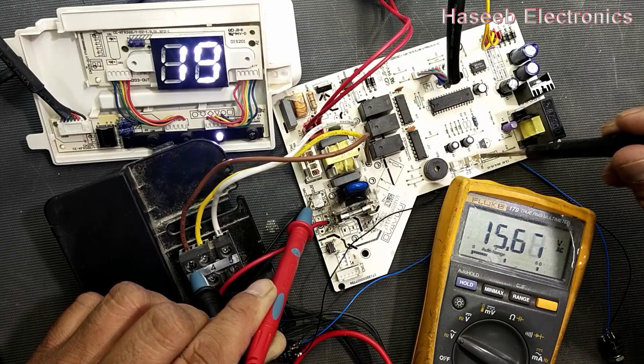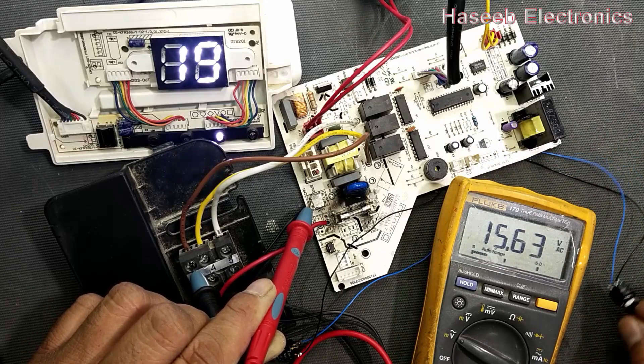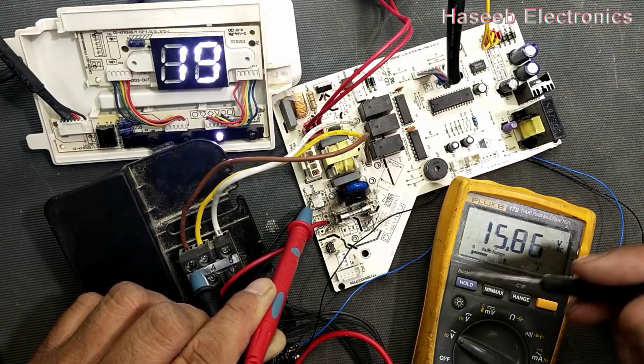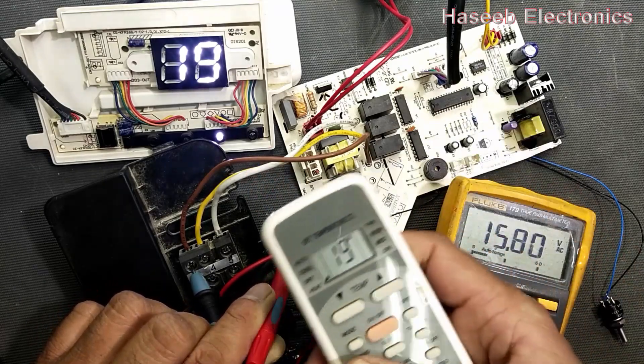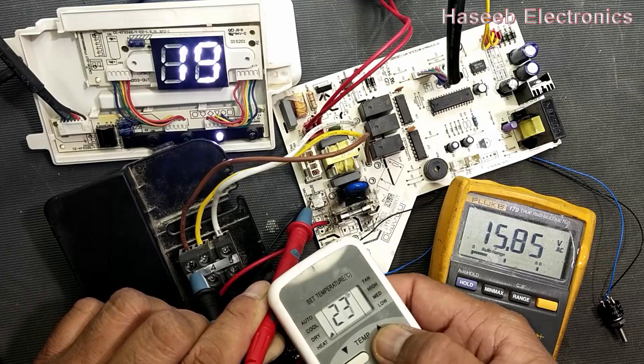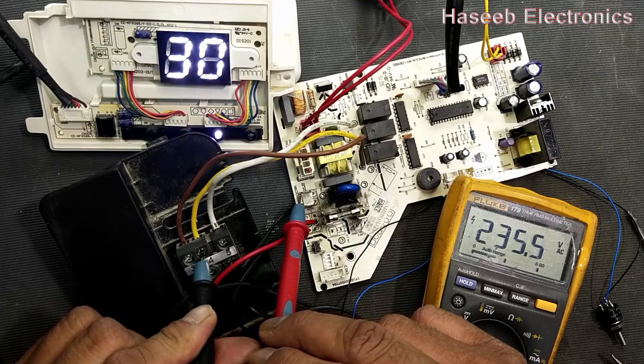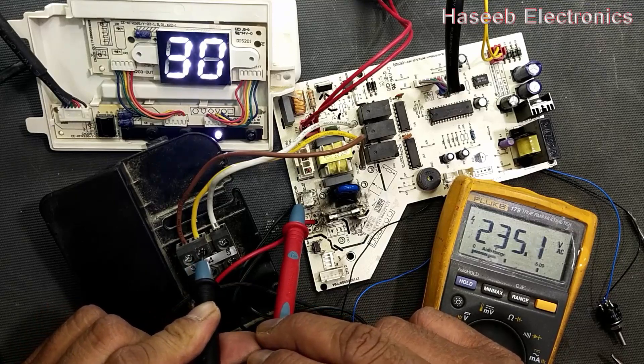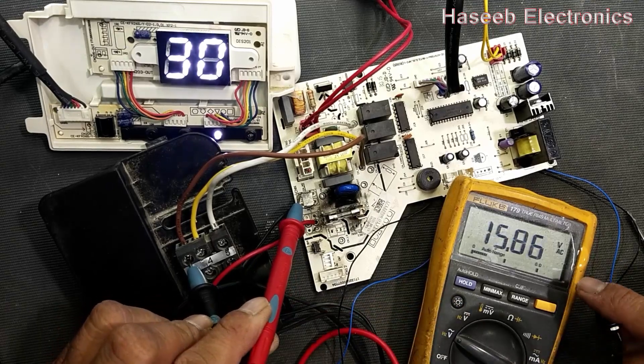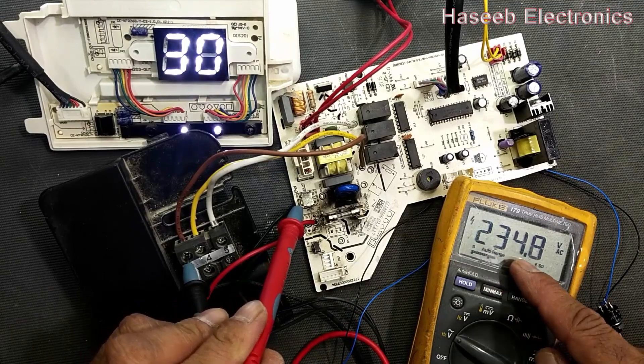We removed the original sensors and are using potentiometers to generate errors as well, because if we use the original sensors we cannot generate errors. The system is not turning on because I set it to 19 degrees — I need to select the right temperature first. In heat mode the four-way valve must be powered on, and the compressor should start after a delay time — now the compressor is on.